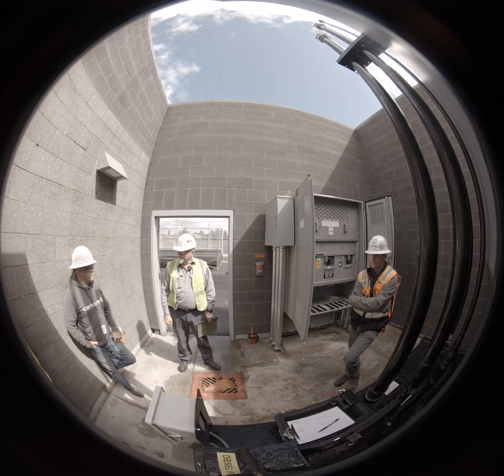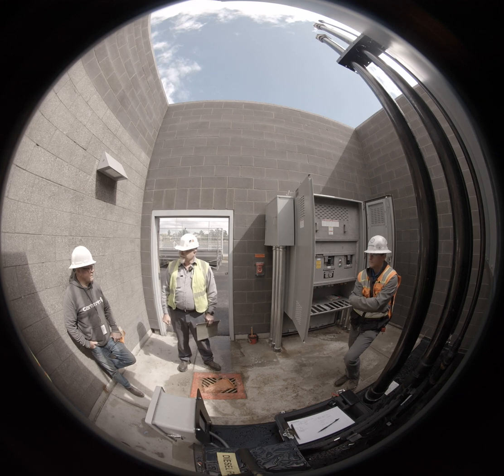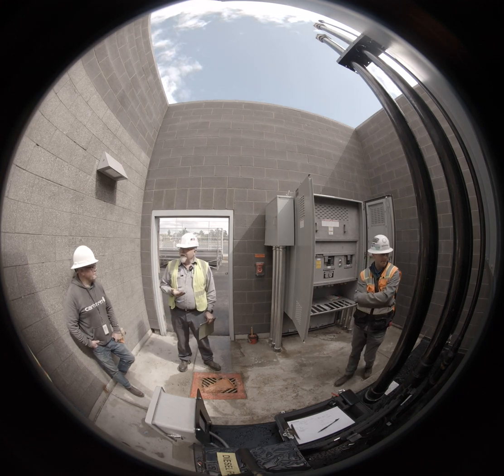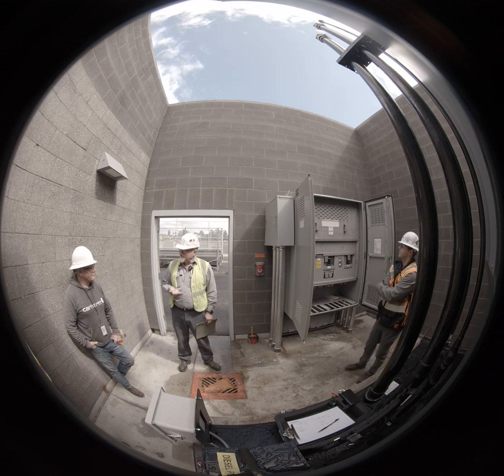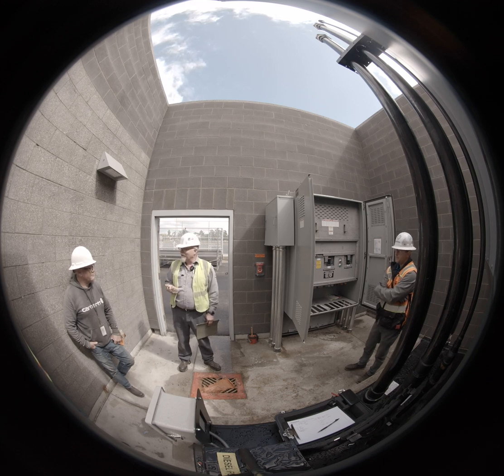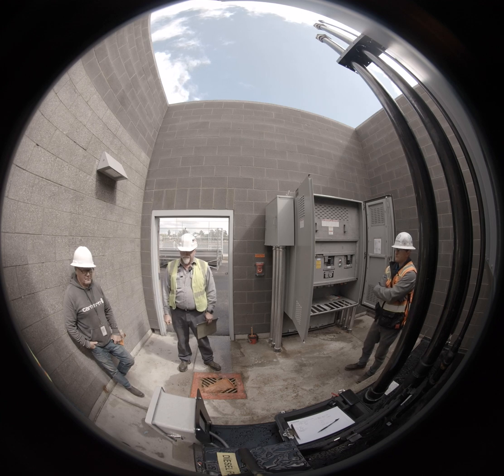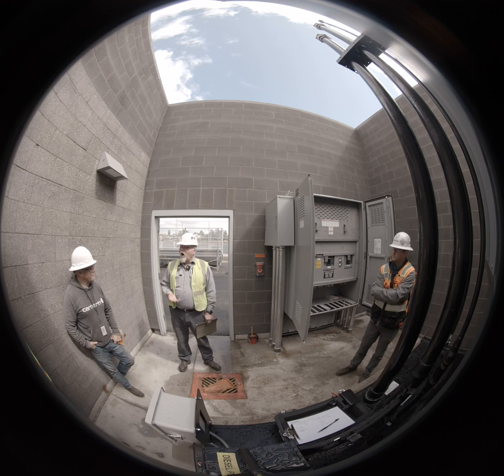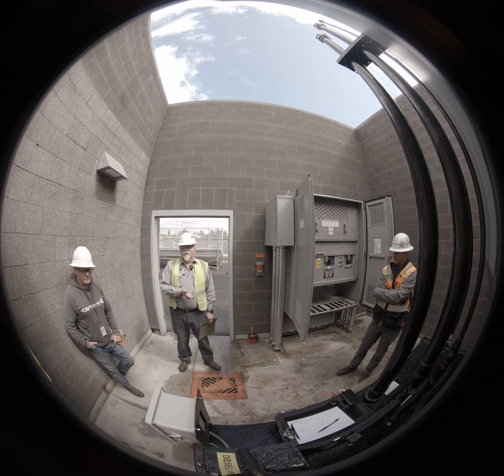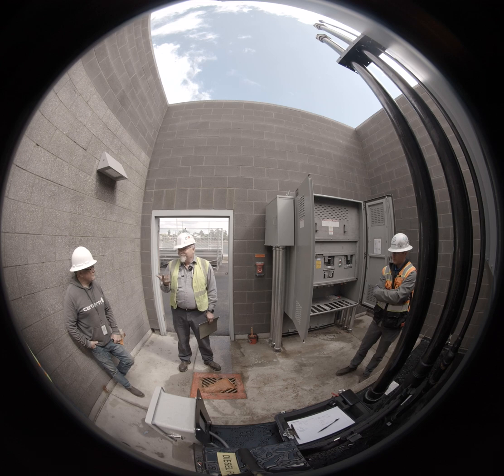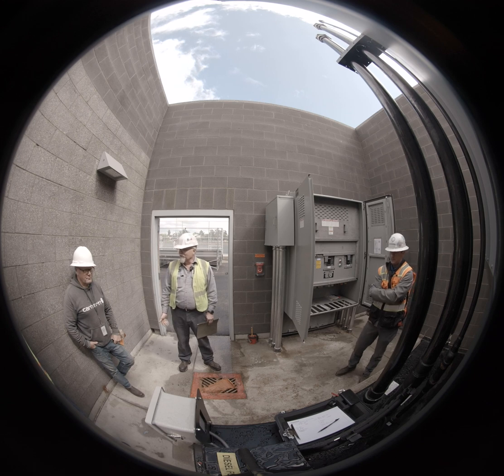You know approximately where the low fuel alarm goes off at? It should be at 50%, yes. Yep, that's a standard. The reason they do that is because you cannot drive this down to the gas station and top off the fuel. So you're calling a truck as well as maybe 10,000 other people that are in that same power outage trying to get fuel. That's why they give you enough time to get fuel back in here before you go lights out. Now, everything is all calculated on the actual load that the generator can put out, not the actual load you have connected. So in reality, you're probably going to burn a third of the rating of this machine or less. Most places are lucky to get third load on them.